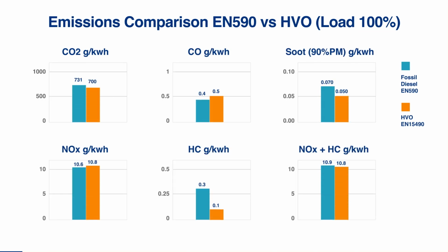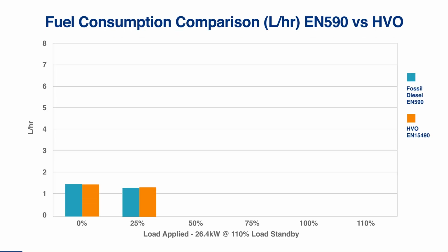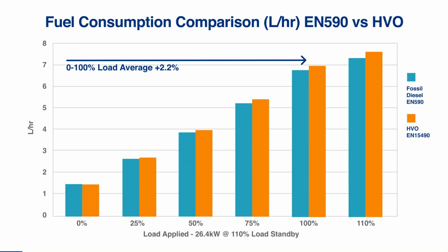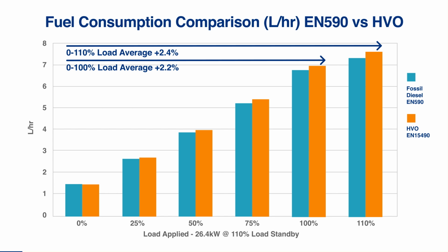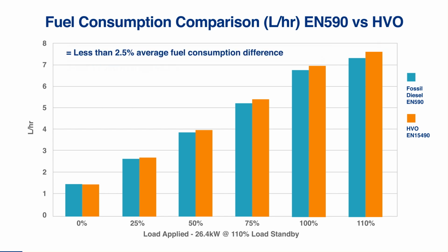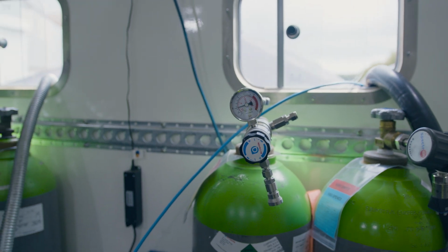What we have found is that the hydrocarbons are a little lower with the fuel we were testing, but generally the exhaust emissions were the same. The other small difference we found was the fuel consumption was a little bit higher, mainly due to the difference in density of the fuel. The density of HVO is a little bit lower than fossil diesel, but HVO has a slightly higher energy value within it, so that offsets some of that fuel consumption difference and brings it pretty close. We were seeing a less than 3% difference in fuel consumption between regular diesel and HVO.